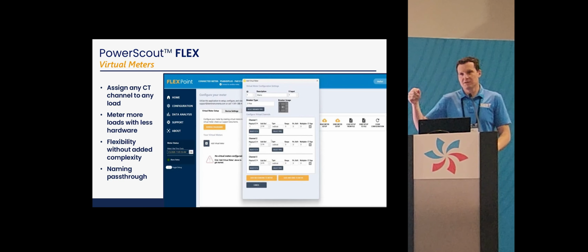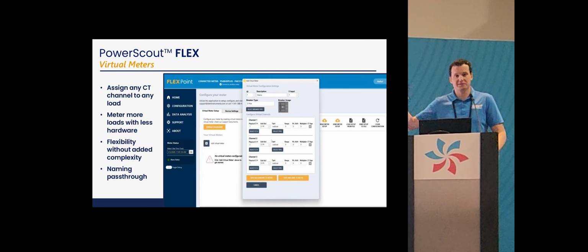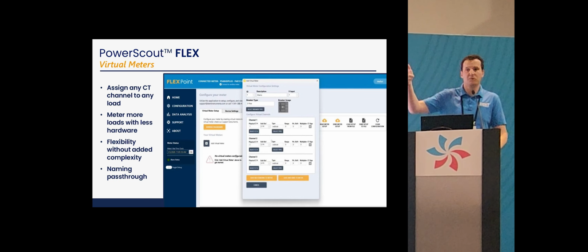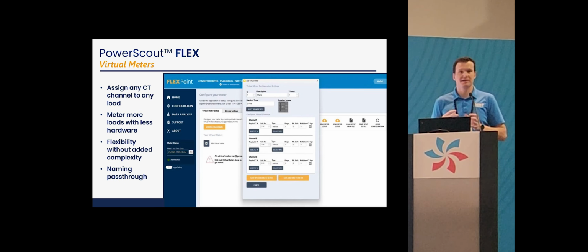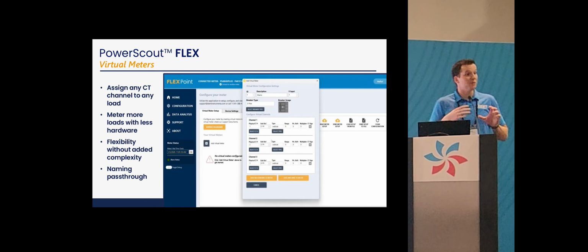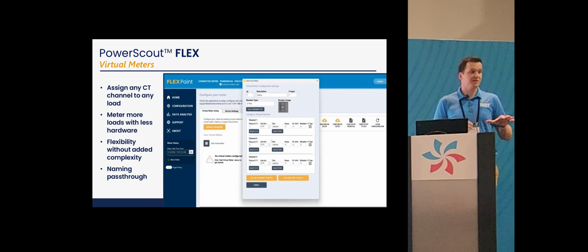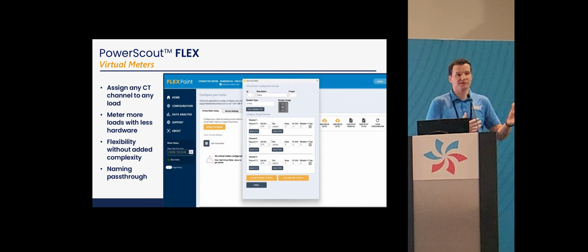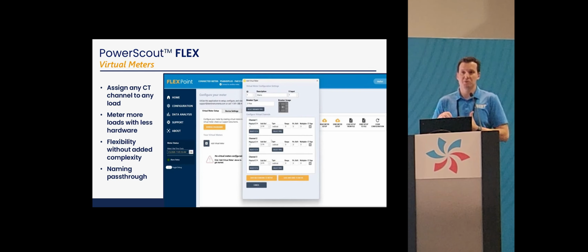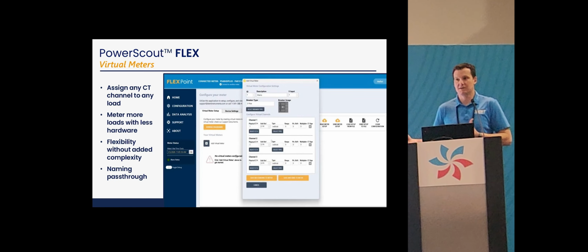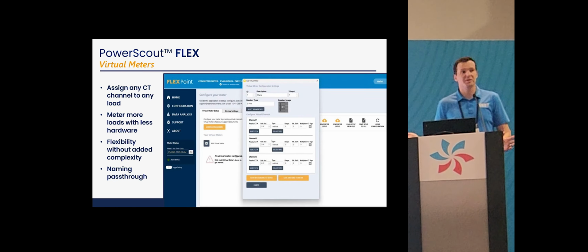And you can mix and match any CTs, so it doesn't have to be in order either. You don't have to choose CT1 and CT2 - you can choose CT1, CT14, and combine it into a virtual meter. The naming that comes across with that makes it much easier for however you're utilizing that data, because the name of that load is actually in the data file. So it makes the setup at your BMS level much simpler.